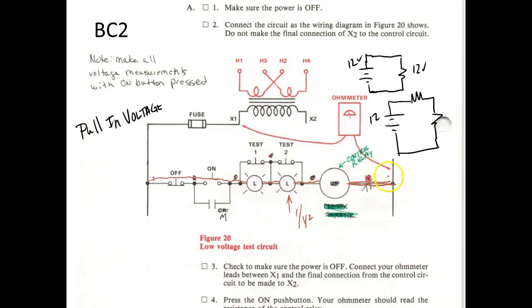And what you're going to do each time is troubleshoot. So you're going to put your black right there, and you're going to start off by jumping right here, and right here, and right here, and measure the voltage just through the circuit. If the relay does drop out when you make these measurements, one of your partners is going to have to hold the button down, because if you don't, you're not proving anything - you're not measuring the voltage that caused it to drop out, you're going to be measuring pretty close to zero.